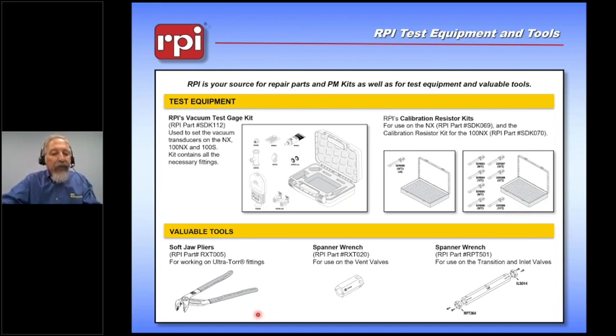In the way of tools, we have a soft jaw plier that's used to open up the Ultra-Torr fittings that are used in various spots in the machine without marring them. We have a spanner wrench to open up the vent valve, which is kind of a different size. We also have repair kits for the vent valves in case you need to repair them. We also have a spanner wrench that is used on the transition and inlet valves, which have a different size from the vent valve.